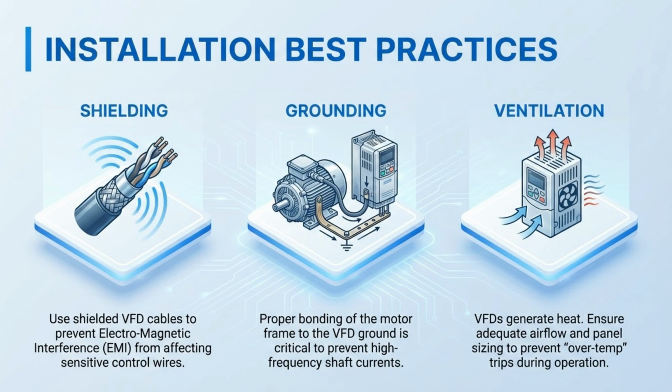For installation best practices, ensure proper shielding with VFD cables to prevent electromagnetic interference. Critical grounding prevents high-frequency shaft currents, and adequate ventilation is necessary to manage the heat generated by VFDs.